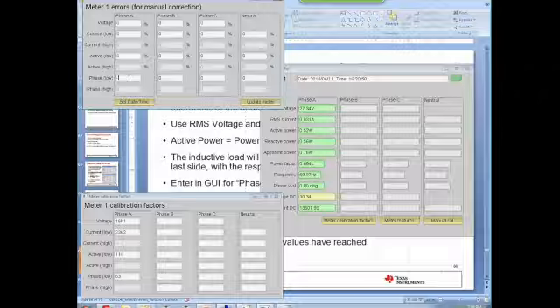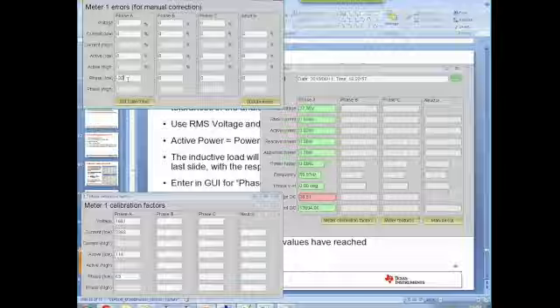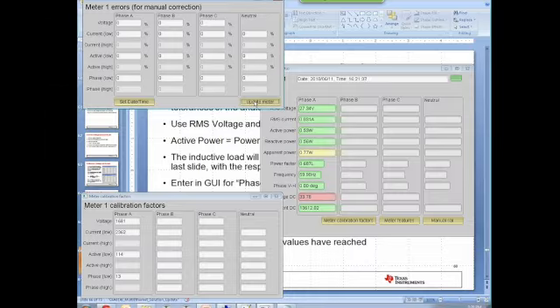I'm going to keep going down on mine. It looks like whenever I go down, my power factor is going up. So I'm going to take my phase correction down even lower here. Sometimes on these calibration values, if you go too far out of bounds, there's not proper sanity checks on them. It lets you do whatever you want. It is possible to overflow the buffers that we have internally in the MSP here, and you can set it to a negative number and not get back properly.